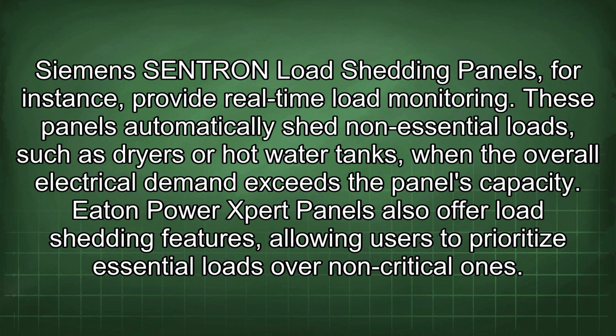Siemens SENTRON load shedding panels, for instance, provide real-time load monitoring. These panels automatically shed non-essential loads such as dryers or hot water tanks when the overall electrical demand exceeds the panel's capacity. Eaton Power Xpert panels also offer load shedding features, allowing users to prioritize essential loads over non-critical ones.